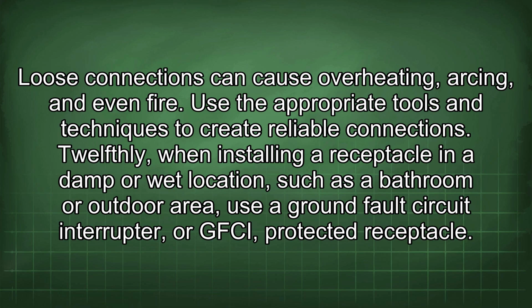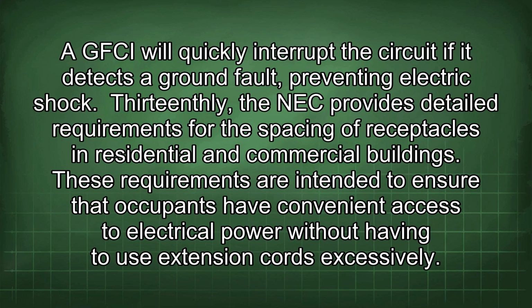12thly, when installing a receptacle in a damp or wet location, such as a bathroom or an outdoor area, use a ground fault circuit interrupter, or GFCI, protected receptacle. A GFCI will quickly interrupt the circuit if it detects a ground fault, preventing electric shock.